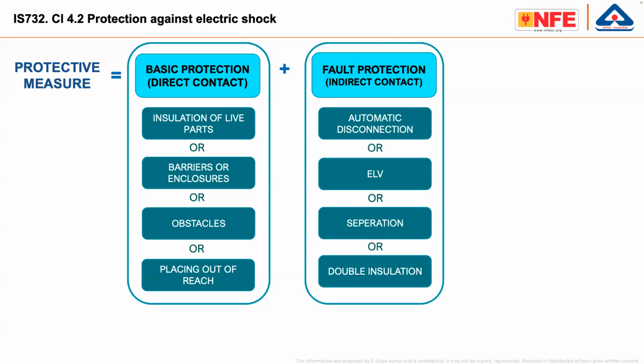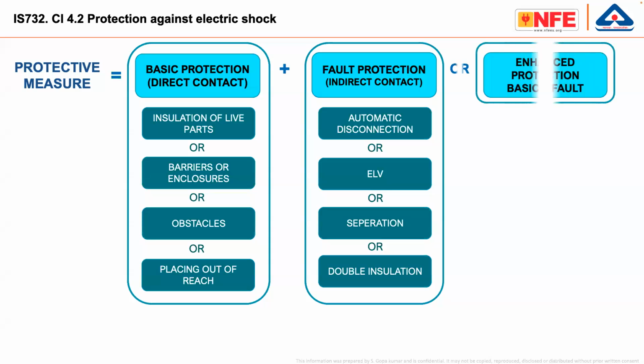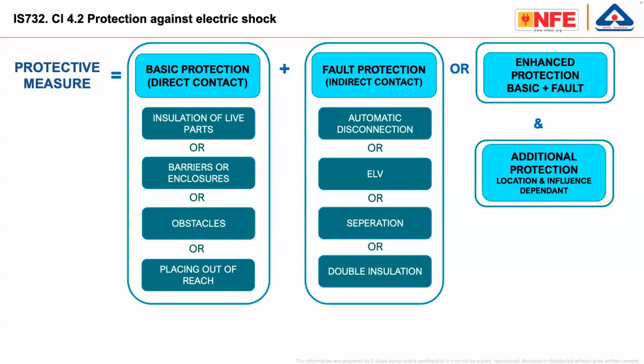So this is the basic scenario. When we read the standard, not only the lift standard but most of the basic electrical safety standards of IEC, it is a better idea to keep this information in mind: basic protection, fault protection, or enhanced protection, which does the job of basic plus fault, so one protective measure doing both basic and fault protection, and additional protection.